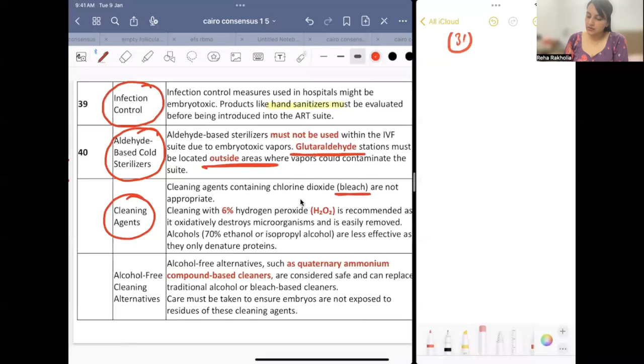Cleaning agent: bleach and chlorine dioxide should not be used. We can use 6% H2O2, hydrogen peroxide, which is recommended as it oxidatively destroys microorganisms and is easily removed. Alcohol, 70% ethanol and isopropyl alcohol are less effective as they only denature protein, so they should not be used. H2O2 will kill microorganisms and it is easy to clean. We cannot have residue of the cleaning agent either. It has to be clean. So H2O2 is easy to clean.